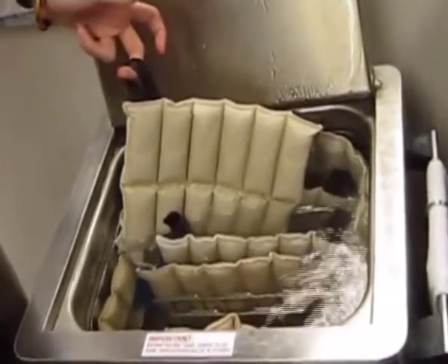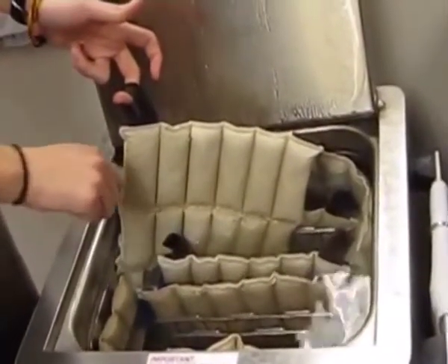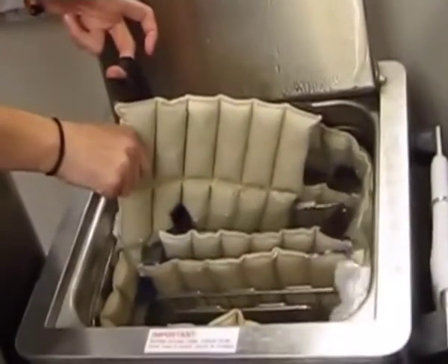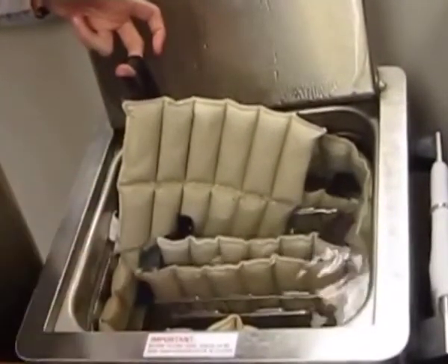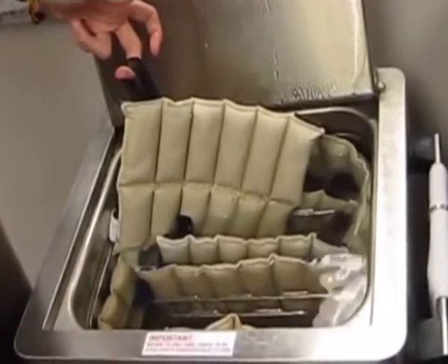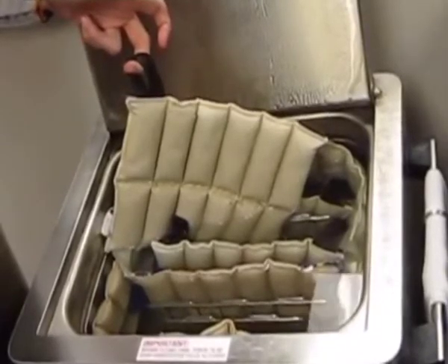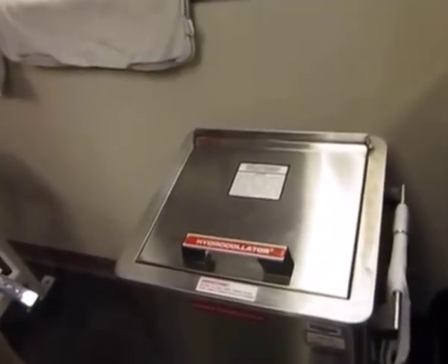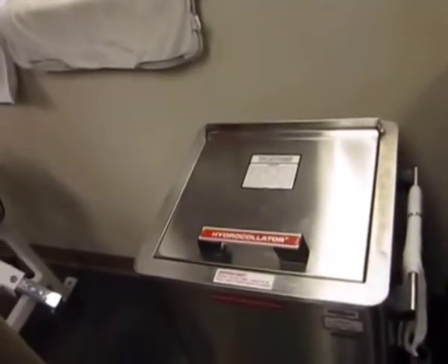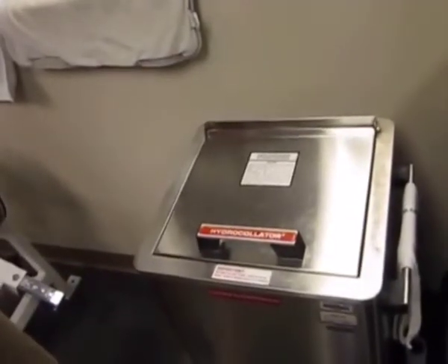This gel will absorb a large quantity of water if it is hot, and provides a considerable store of heat energy. The gel is contained in a set of separated fabric pockets so that the whole pack is flexible and the gel is confined. They are heated by being placed in a special tank of water warmed to 70 to 80 degrees Celsius by an electric heater controlled by a thermostat. It takes about 2 hours to become fully heated from cold but less when reheated.